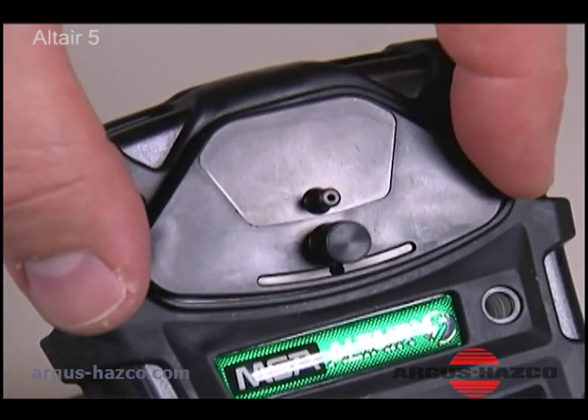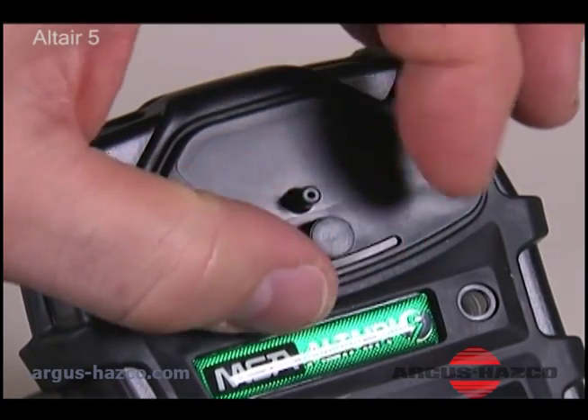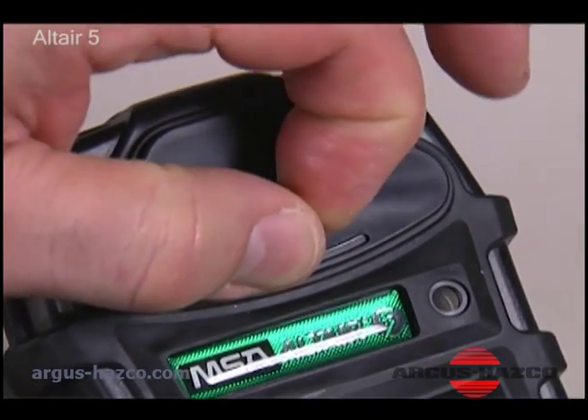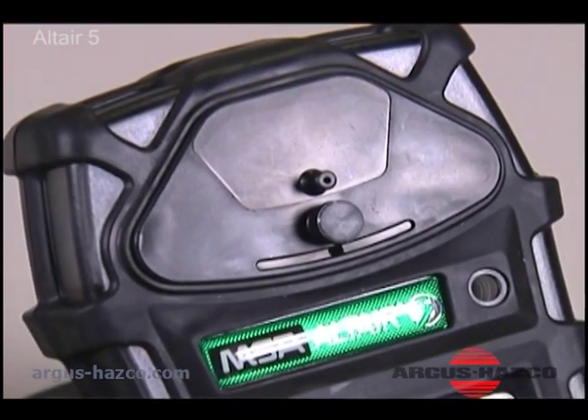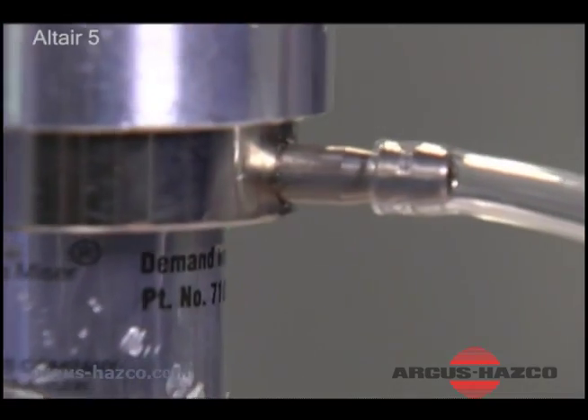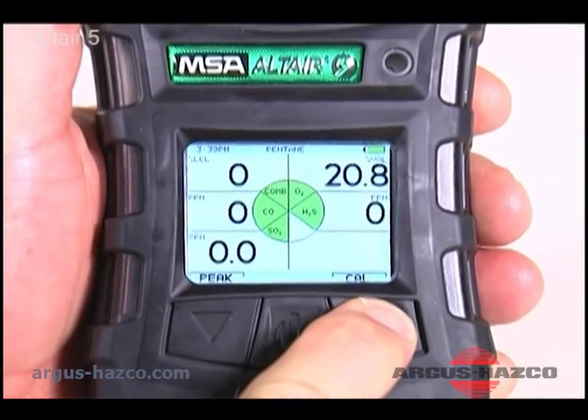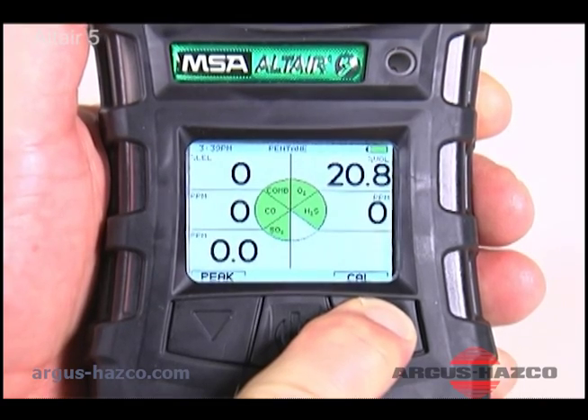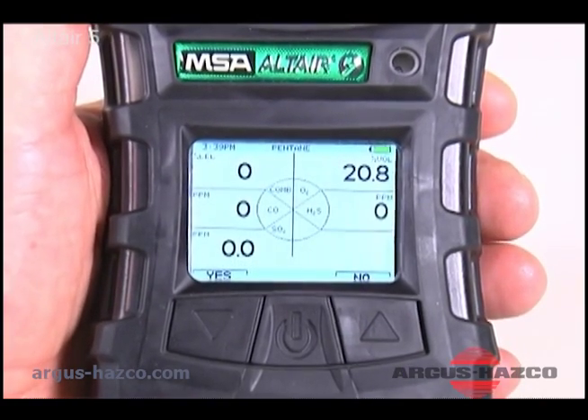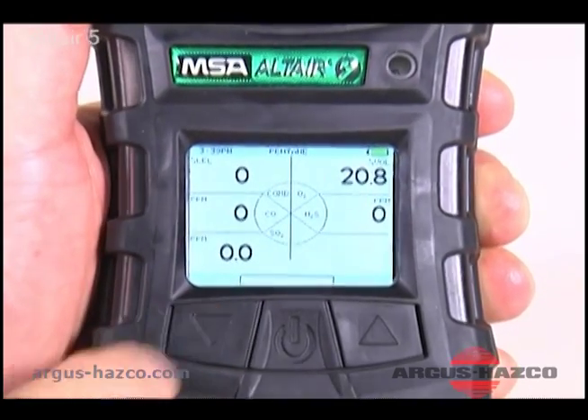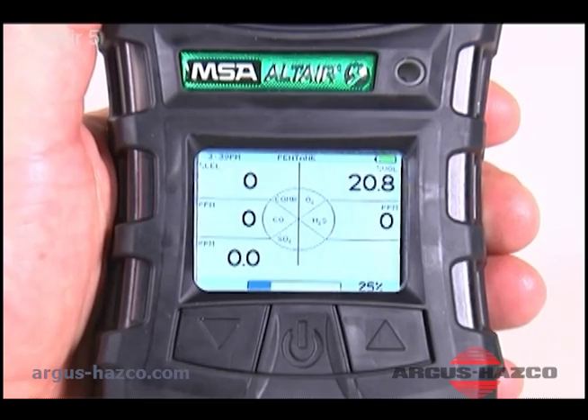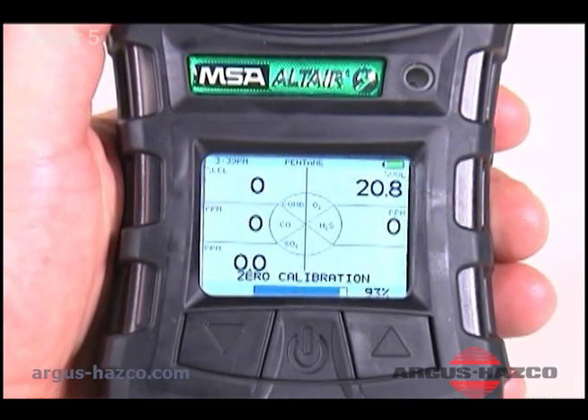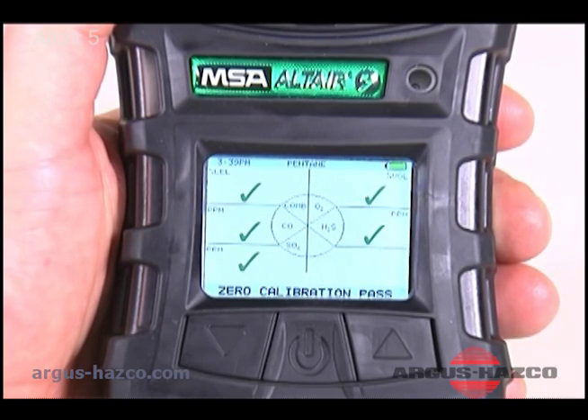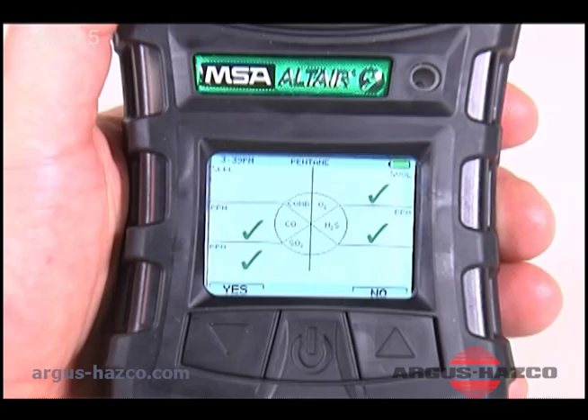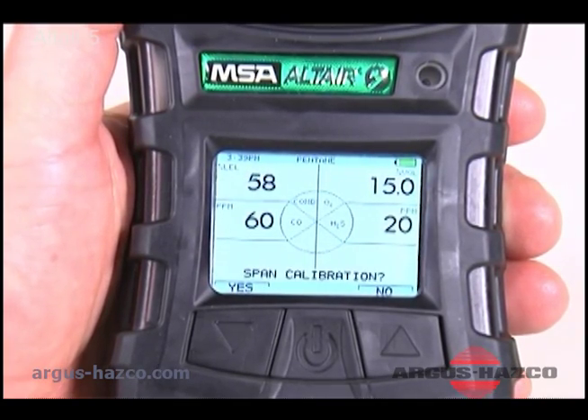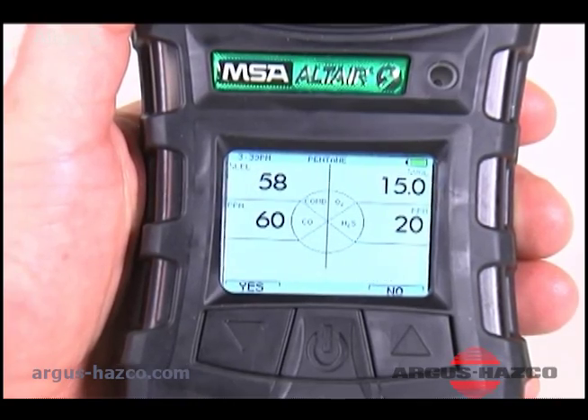Connect the calibration cap to the instrument. Ensure that it is oriented correctly. Connect the end of the tubing to the cylinder regulator. Navigate to the measurement mode screen and press and hold the up arrow button until 0 calibration flashes. Press the down arrow button for yes. Span calibration flashes. Press the down arrow button for yes.